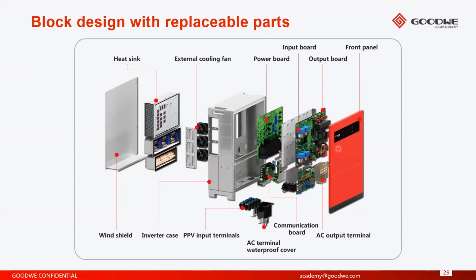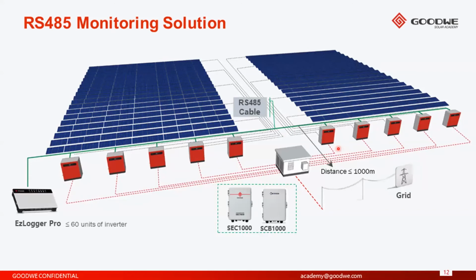In terms of the monitoring solutions we offer, we have the standard, traditional RS485 monitoring solution, which means that all the inverters on site are daisy chained with communication to each other. One of the main advantages of RS485 is that you can have distances of up to 1,000 meters, so you can cover quite a large PV array with an RS485 communication cable. With our EzLogger Pro, you can connect up to 60 inverters, regardless of the size. It can be a 1 kilowatt inverter or a 120 kilowatt inverter. We also have the SEC 1000 and SCB 1000 all-in-one monitoring solution, which I touch on later in the webinar.